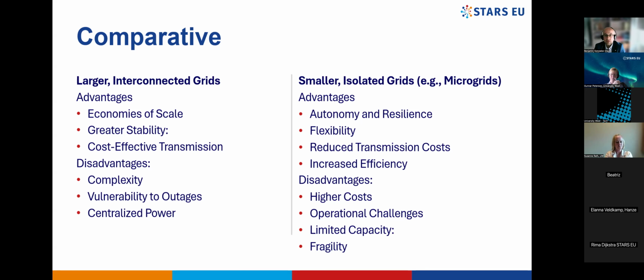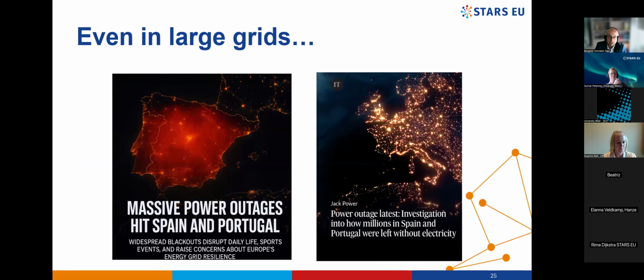Considering this, it's perhaps more frequent to see a blackout in an isolated system. Systems at the European level are more stable, but even in larger grids we can experience power outages or blackouts. These things are not usual, there's a very low probability of them happening, but when present inside the system, they can occur, and when something happens, the system can collapse. Even in large grids this happens - imagine in small grids, where you don't have the backup of another country to provide energy and help restart.